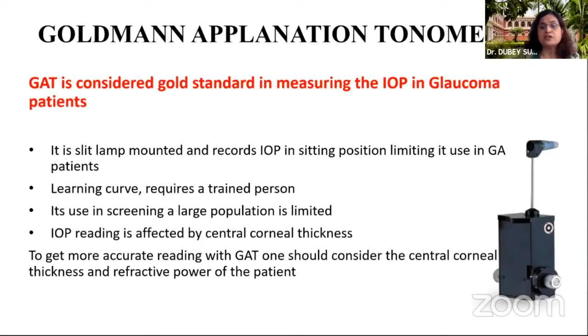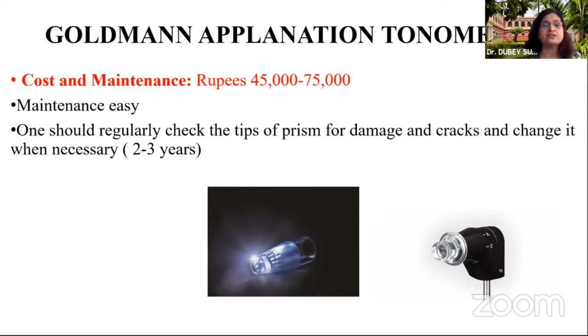As far as cost is concerned, it is 45,000 to 75,000 rupees, so expensive. However, maintenance is easy, and one should regularly check the tips of the prism for damage and cracks and change it when necessary, especially when we are frequently dipping it into sodium hypochlorite solution for disinfection during COVID times. So disinfection in between patients is done by 70% isopropyl alcohol wipes at the tip of the prism for 10 seconds. However, it doesn't remove the adenovirus. It does disinfect against the COVID virus.